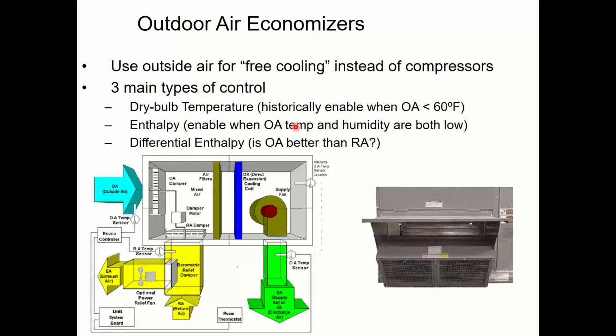That means I'm just going to look at the straight up temperature. I don't care about humidity, not my problem right now. Dry bulb economizer, dry bulb temperature. So I have an outside air temperature sensor sitting on this unit, and if my system asks for cooling, and I look outside and let's say, for example, it's less than 60 degrees out, don't turn the compressor on. Just open up the damper and give me the free cooling. But if I look at it and it's 82 out, well, don't do that. Sucking 82 degree air in isn't going to help me. I'm already hot. Leave the damper at minimum ventilation position and run the compressor, right? That's how that's going to work.